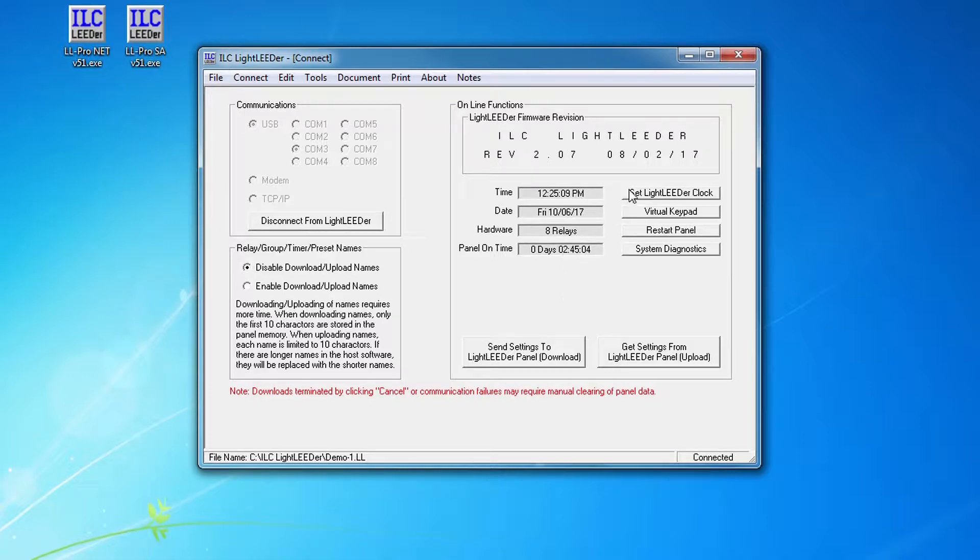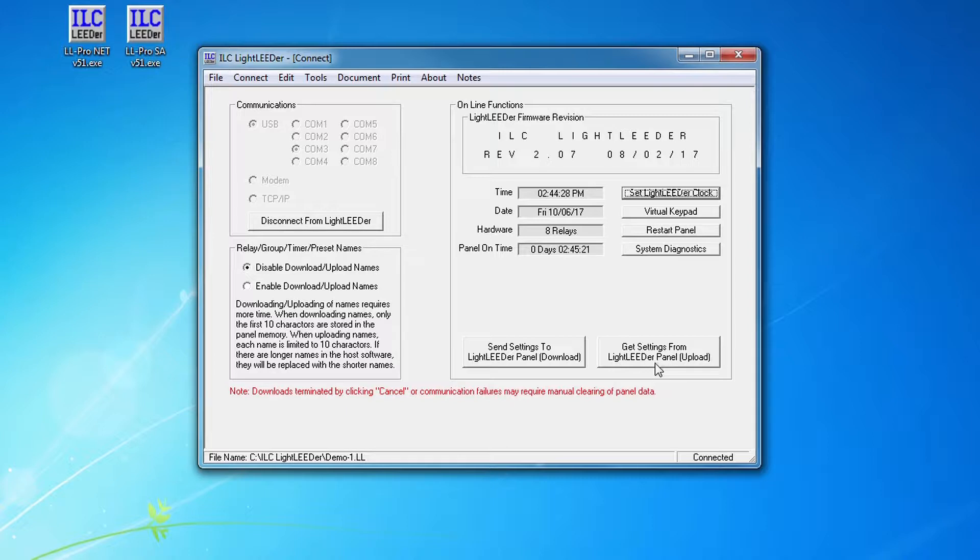I can set the clock in the panel using the Windows clock on my computer, but the first thing I'm going to do is - I've got send settings to Light Leader panel download. I'm looking to upload settings from the panel first because I've already hand programmed a number of switches and some control functions, so I'm going to get settings from Light Leader panel. I'm going to click on the upload button.